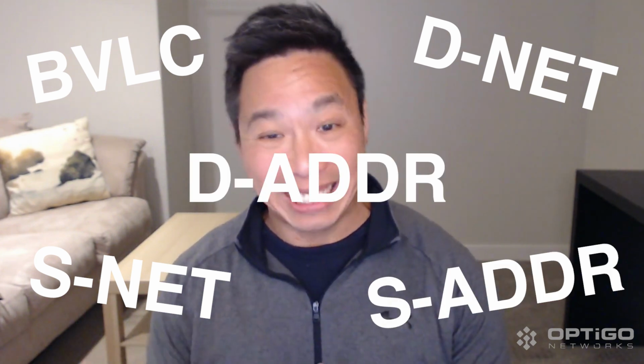Yeah, great question. This is where we get into the different nomenclatures and shortcuts that we use in the BACnet world. Sometimes you hear someone talk about a BVLC or DNet or SNet or SAdr or DAdr. It's just because a few of us have been working in the world of BACnet so long that we're short-forming destination network into DNet, and source network into SNet. These are different fields, part of a BACnet packet, more particularly part of the network protocol of the BACnet standard. It's a way to say this packet is going to this BACnet network.